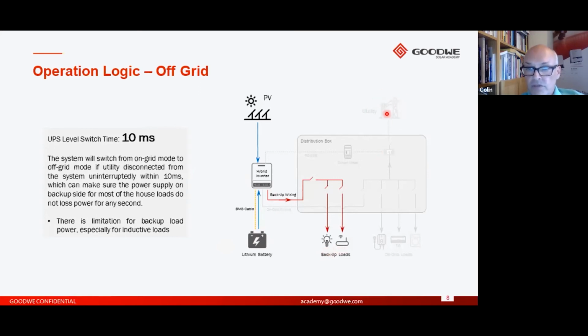Now, when we lose the grid, you can quite seamlessly see that these devices, whatever's on this load here, will be supported, and it's within 10 milliseconds. As I say, it's more or less a UPS supply. This can only support the output power rating of the AC backup port. If you go over that, you'll overload the inverter and it will actually switch down, so it can't damage the inverter.